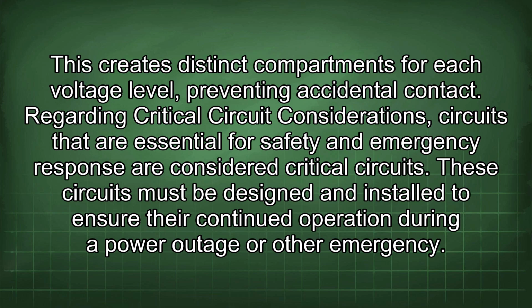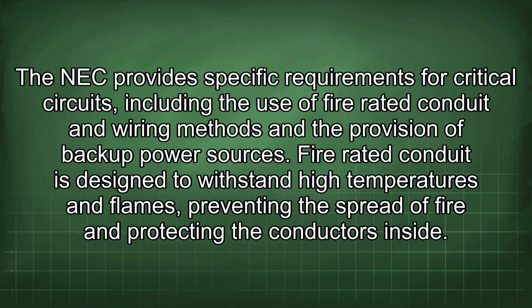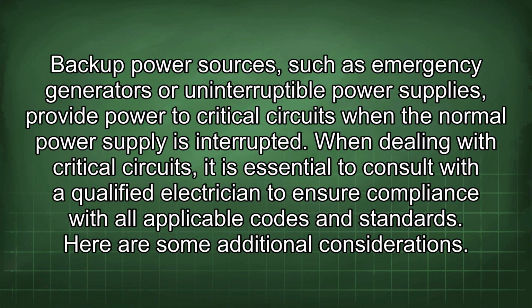Regarding critical circuit considerations, circuits that are essential for safety and emergency response are considered critical circuits. These circuits must be designed and installed to ensure their continued operation during a power outage or other emergency. The NEC provides specific requirements for critical circuits, including the use of fire-rated conduit and wiring methods and the provision of backup power sources. Fire-rated conduit is designed to withstand high temperatures and flames, preventing the spread of fire and protecting the conductors inside. Backup power sources, such as emergency generators or uninterruptible power supplies, provide power to critical circuits when the normal power supply is interrupted. When dealing with critical circuits, it is essential to consult with a qualified electrician to ensure compliance with all applicable codes and standards. Here are some additional considerations.